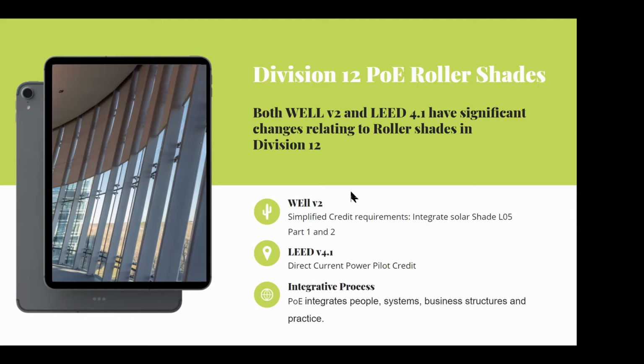With LEED 4.1, we look at the direct current power pilot credit, which you've probably heard us talk about, or heard on the street. Under option 1, where you have individual systems like lighting as the major loads, they don't address shades there. But when you look at the building holistically, and use low voltage power distribution for shades such as PoE, we can help contribute to that energy model when trying to get that possible 18 points.